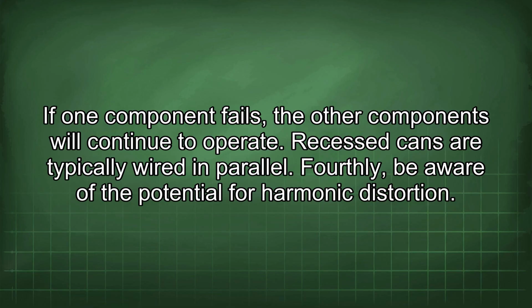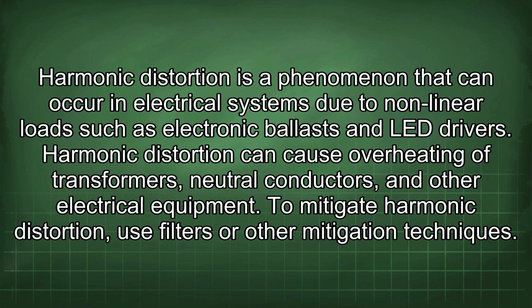Fourthly, be aware of the potential for harmonic distortion. Harmonic distortion is a phenomenon that can occur in electrical systems due to nonlinear loads such as electronic ballasts and LED drivers. Harmonic distortion can cause overheating of transformers, neutral conductors, and other electrical equipment. To mitigate harmonic distortion, use filters or other mitigation techniques.